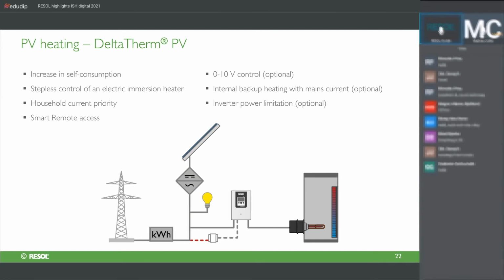The DeltaTherm PV controller transfers power directly to an electric heating element. What makes it special is that it is provided stepless to the heater, meaning it can forward even a small amount of excess current and modulate the heating element according to the available power. Compared to the PHM, we have integrated power electronics in the DeltaTherm PV that enable this modulation and stepless control.